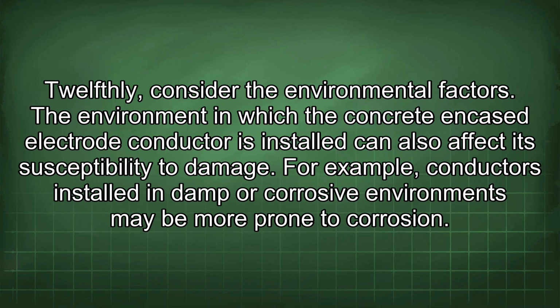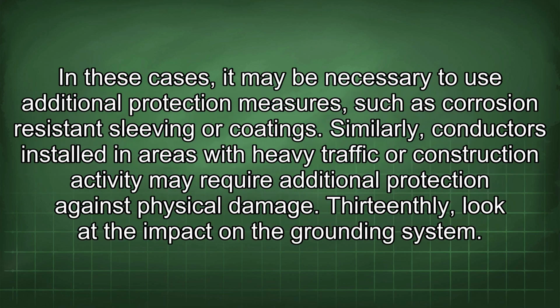12thly, consider the environmental factors. The environment in which the concrete encased electrode conductor is installed can also affect its susceptibility to damage. For example, conductors installed in damp or corrosive environments may be more prone to corrosion. In these cases, it may be necessary to use additional protection measures, such as corrosion-resistant sleeving or coatings. Similarly, conductors installed in areas with heavy traffic or construction activity may require additional protection against physical damage.